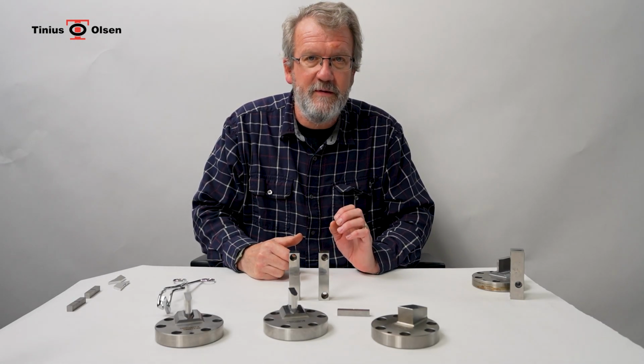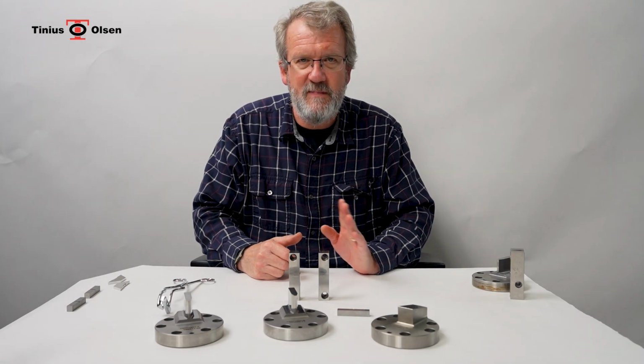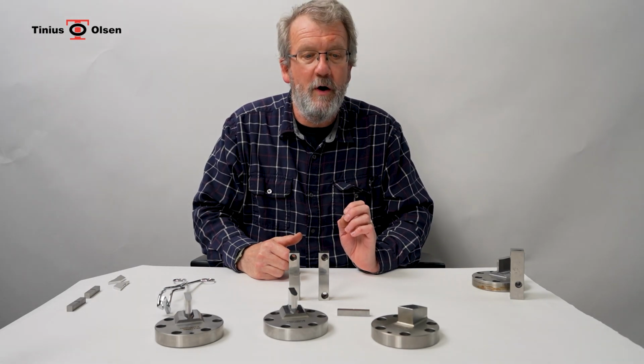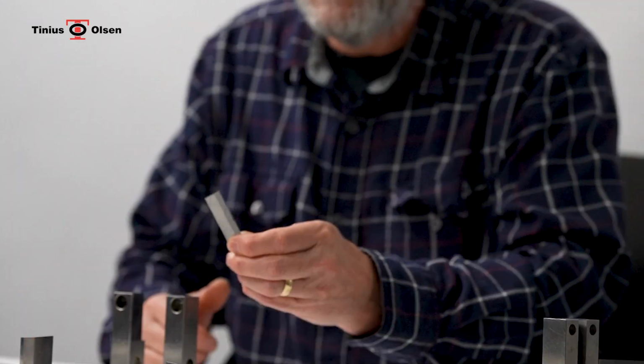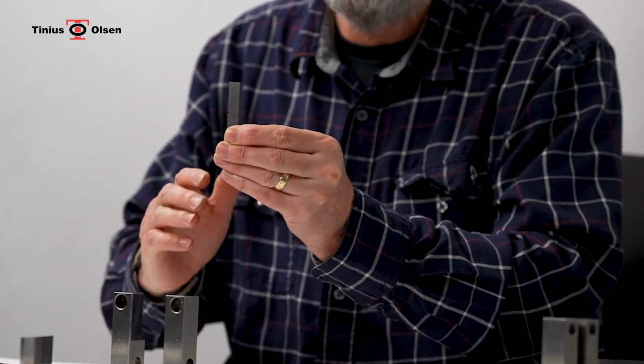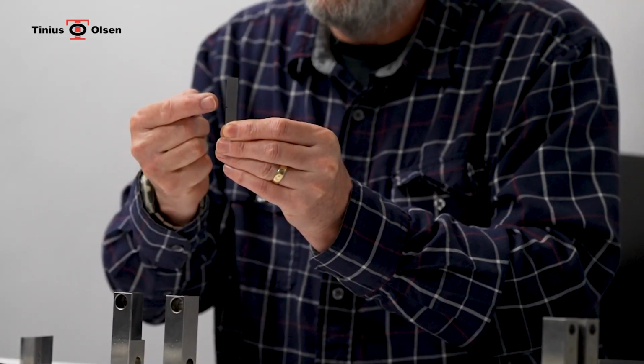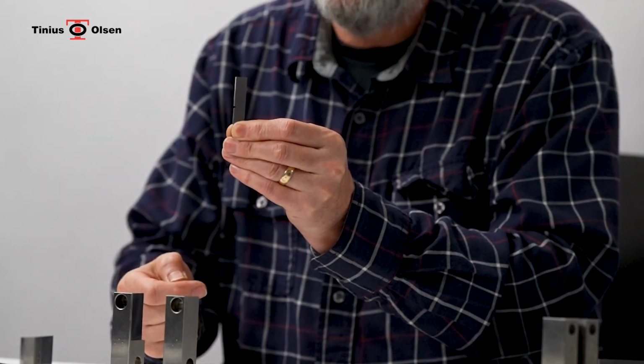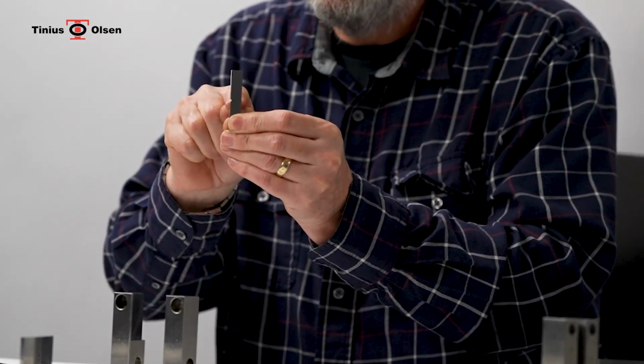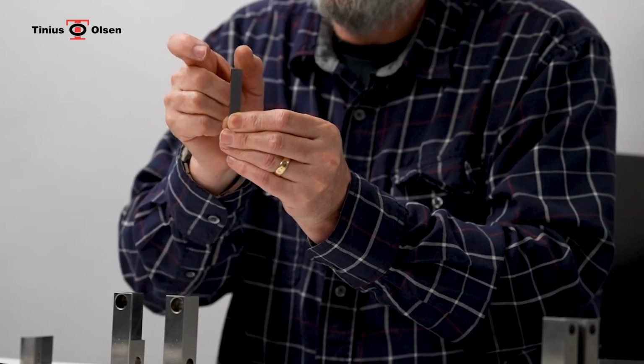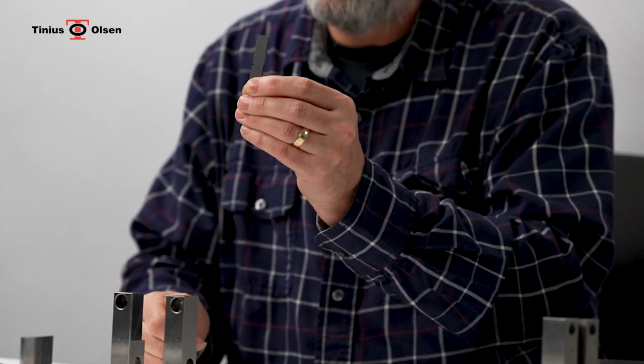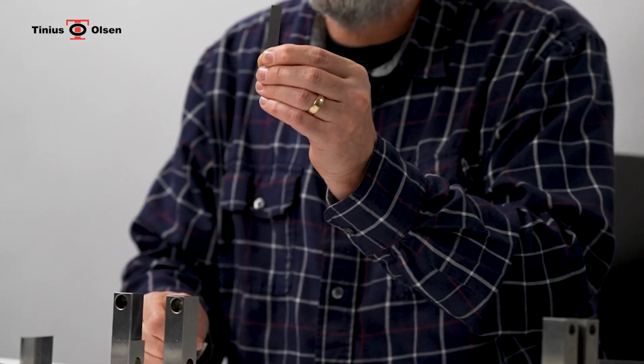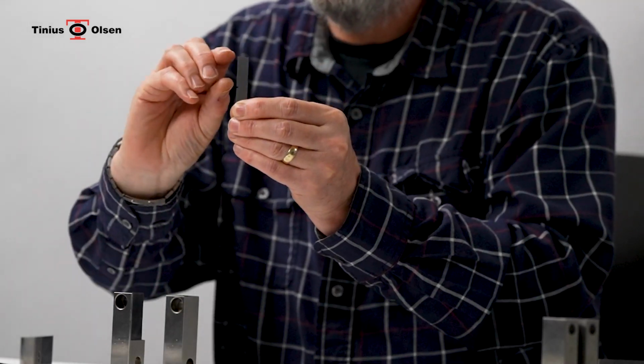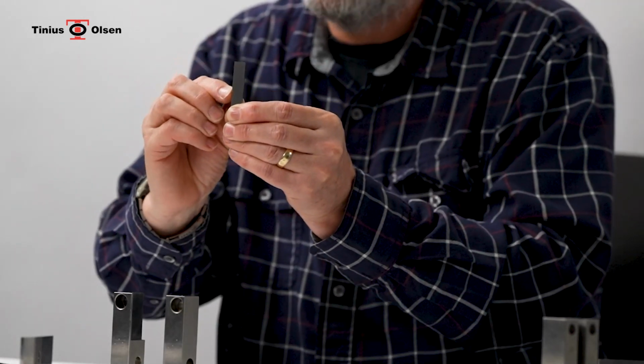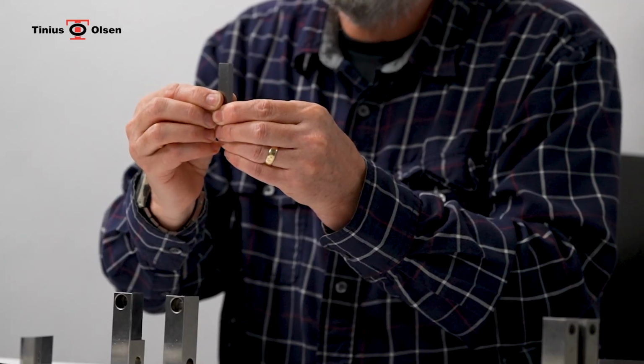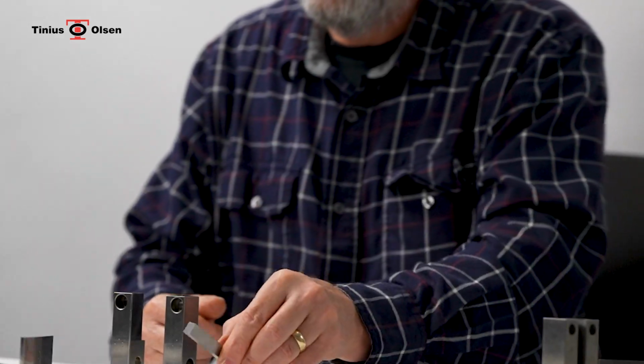Before we go any further, there are two basic test methods for impact. One is IZOD, where a sample is mounted vertically, like the letter I, with the notch on the side that is struck. The sample is hit and it breaks at the notch and folds over, just like a stick. For an IZOD test, you would need a clamp, and you also need some accessories to allow the notch to be located correctly in the machine, and then it can be tested.